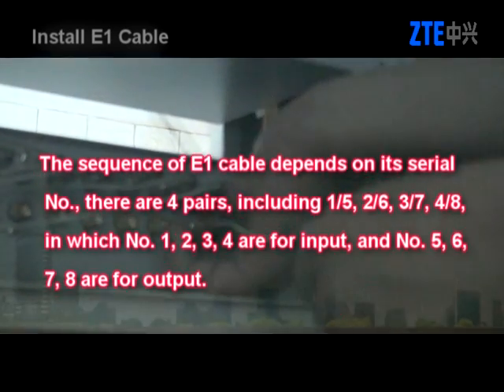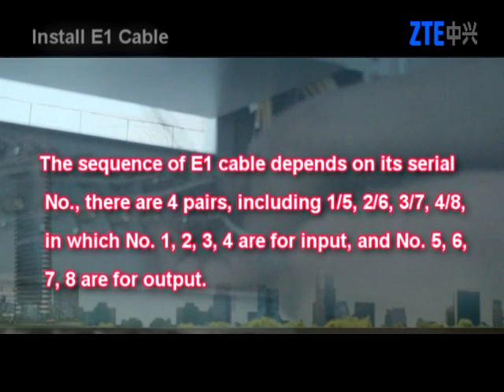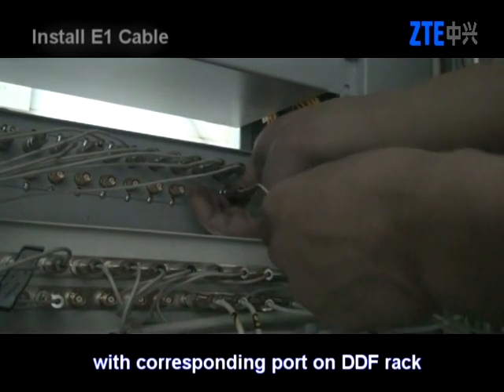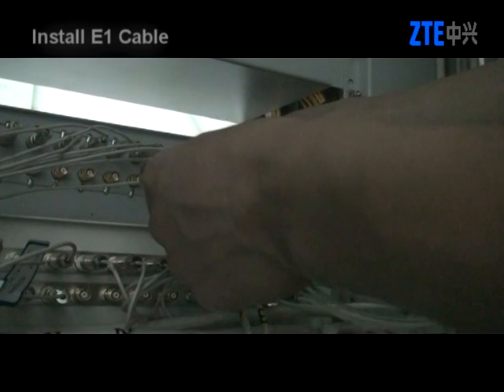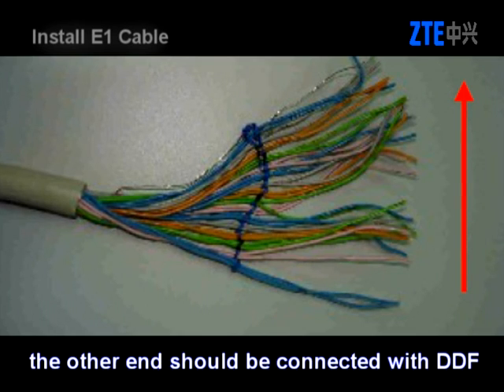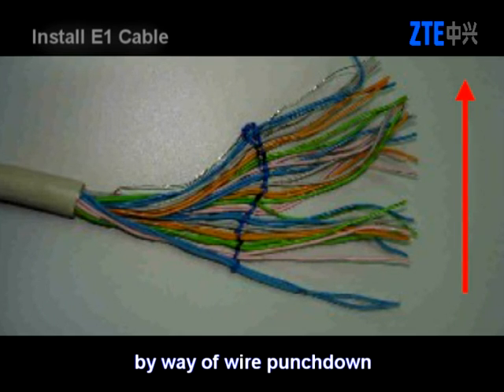The sequence of E1 cable depends on its serial number. There are four pairs: 1-5, 2-6, 3-7, and 4-8, in which numbers 1, 2, 3, 4 are for input and numbers 5, 6, 7, 8 are for output. Connect the other end of the E1 cable with the corresponding port on the DDF rack. If a 120-ohm E1 cable is adopted, the other end should be connected with the DDF by way of wire punchdown.